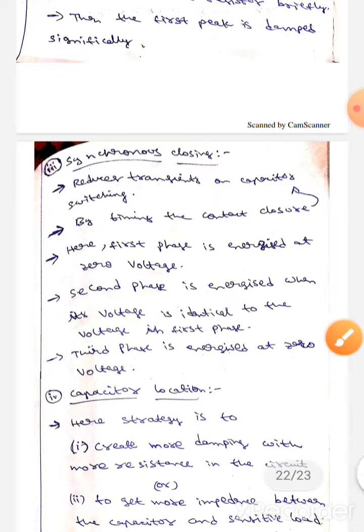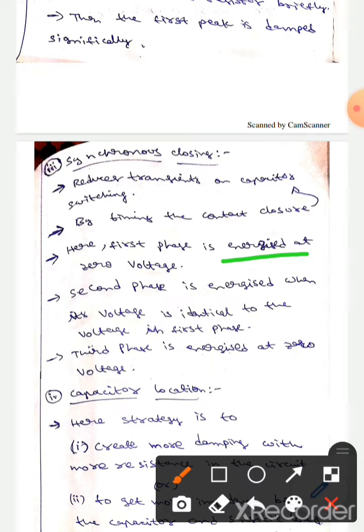And also here, first phase is energized at zero voltage. Second phase is energized when its voltage is identical to the voltage in first phase. Third phase is energized at zero voltage.